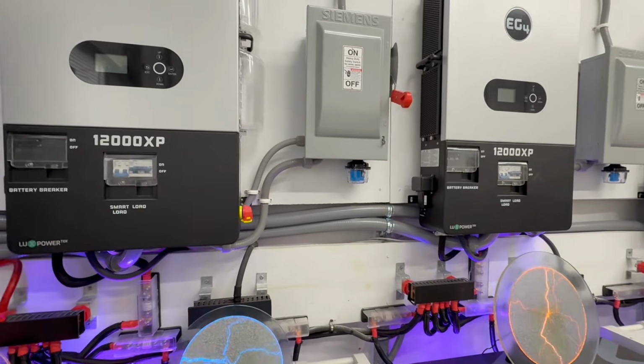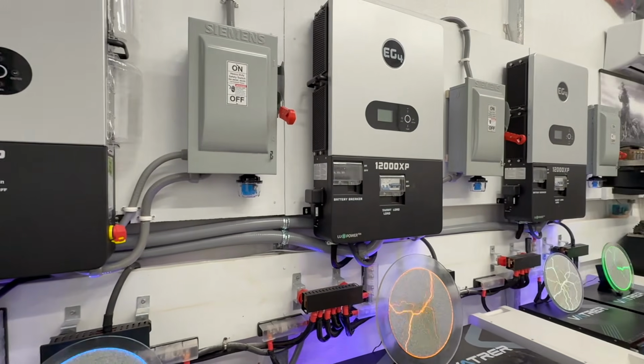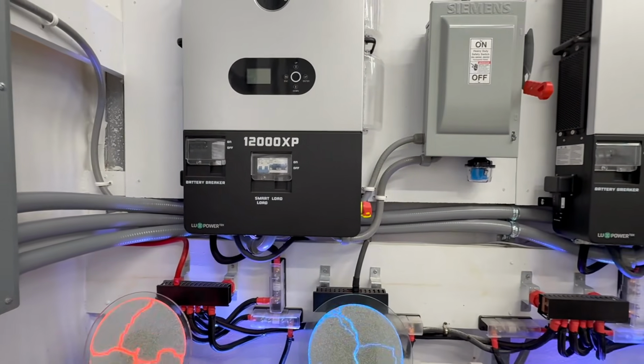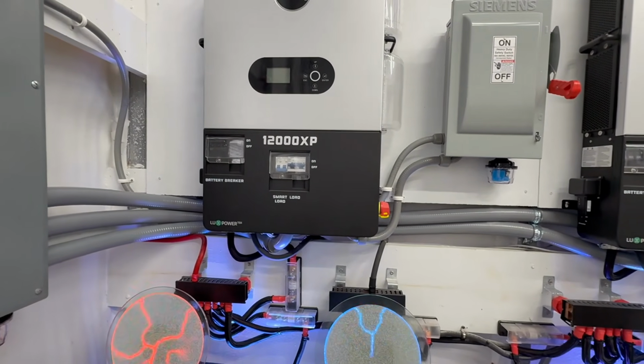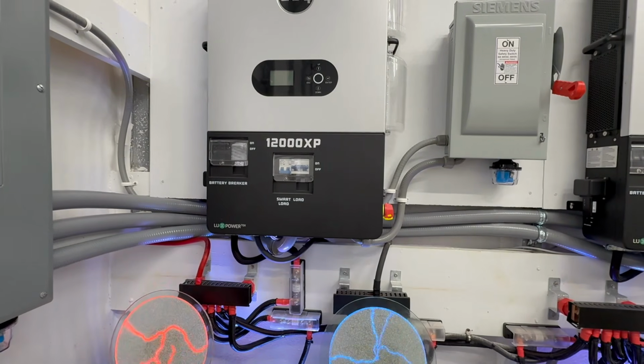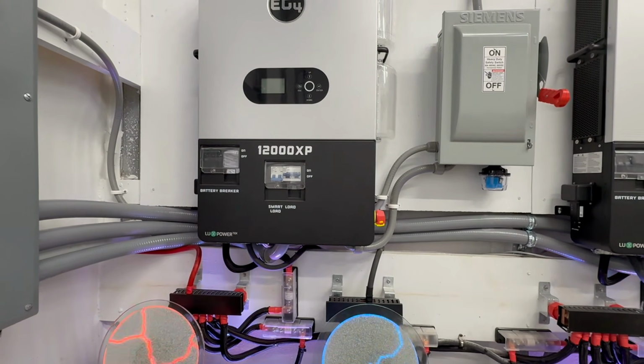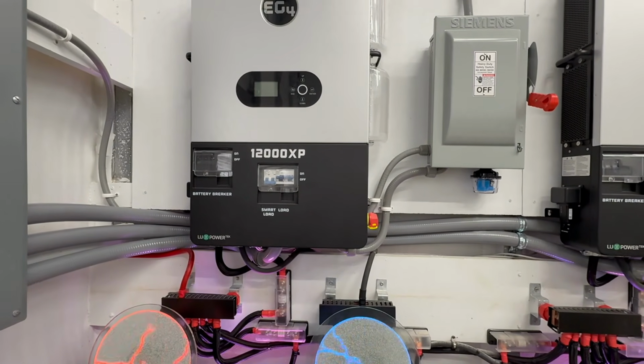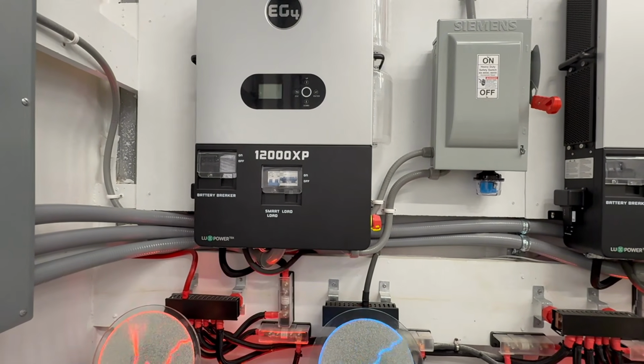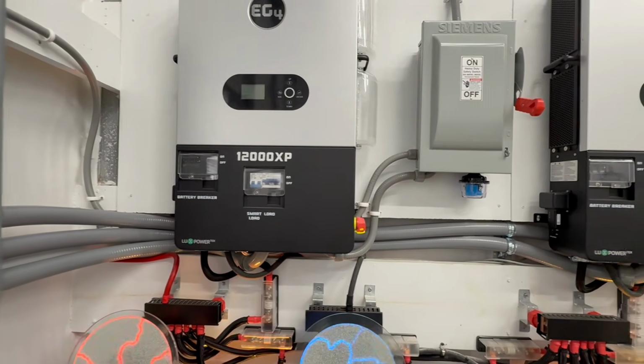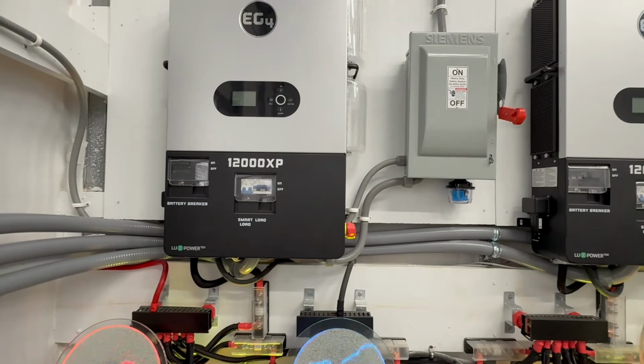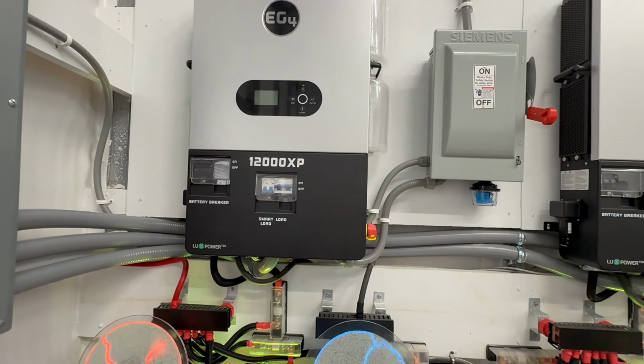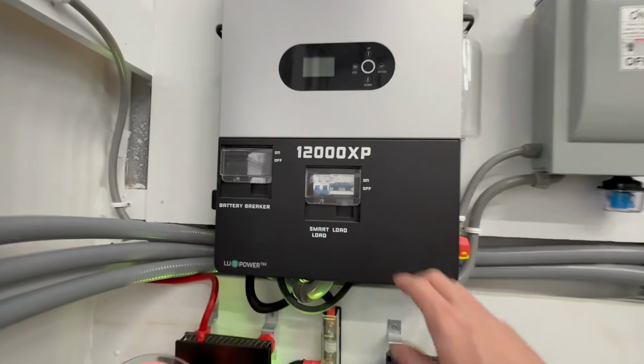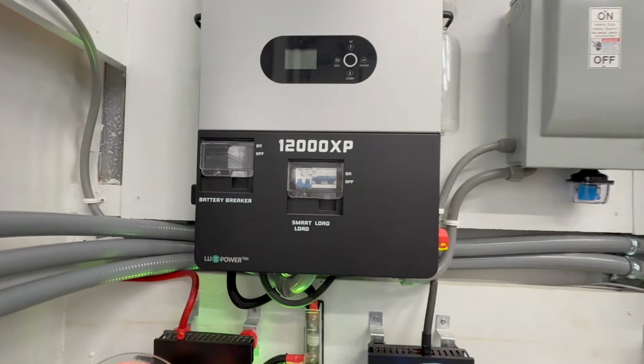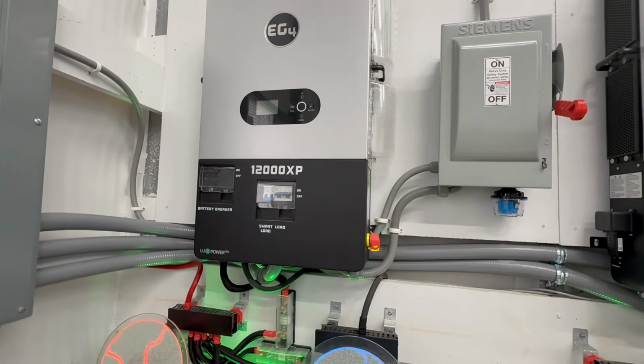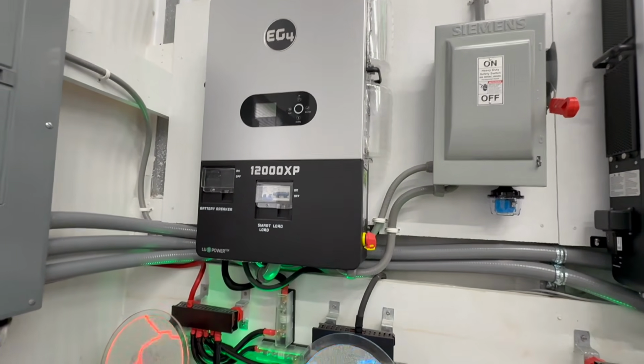Now, this is for the folks that are DIY and have the 12,000 XP, something you need to know. If you have these powered off and you have the circuit breaker still turned on, you still have power flowing into your 12,000 XP to keep the DC capacitors still charged. So if I go to flip these back on now, there will not be a surge to the inverters. But if I was to flip down these battery disconnects, then there would be. So typically, I don't touch that battery disconnect there.